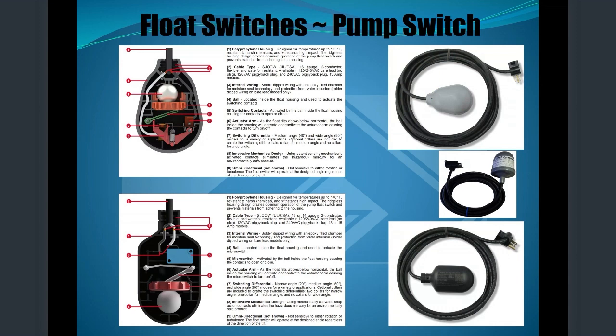Here are the internals of our Relion on the top left. We have different collars in there. We have the same housing for our narrow, medium, and wide angle float switches, but then we put different collars in there so that the metal ball either has to drop down and climb up over the ridge to give us a wide angle, or narrow angle, or medium, or we put both collars in, or one collar on the other side. And I wish I would have brought one open with me. But it just determines the activation angle. And then on the bottom left, we have the micro switch, and the same principle there. We have different collars to get the activation angles. Just kind of gives you pictures on the right.